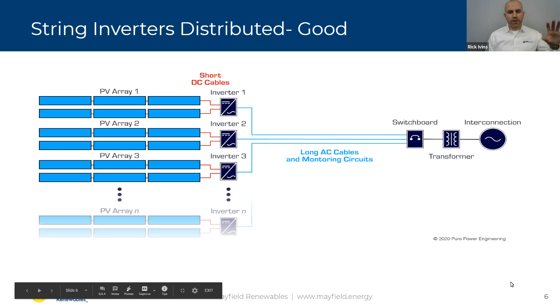That article really goes into the three major categories of ways to lay out your ground mount site. It could apply to rooftops too, but we'll mostly talk about ground mount here. The first of the three options, which is a good one, is where you have your string inverters distributed throughout the array. If you've got a bunch of rows of solar panels, you can put an inverter for these 3 rows, then a little further down another inverter for those 3 rows, and another inverter a little further down.